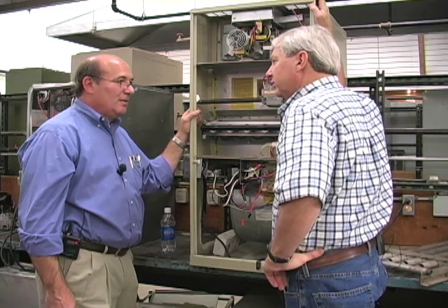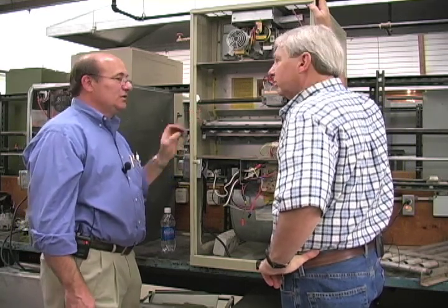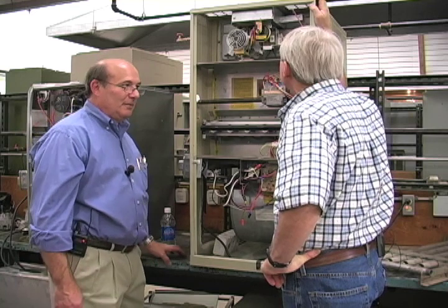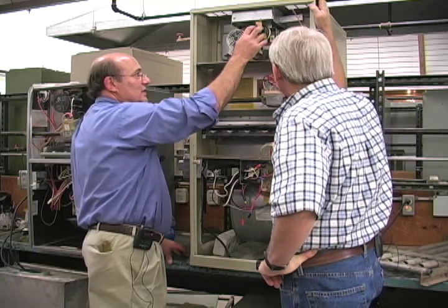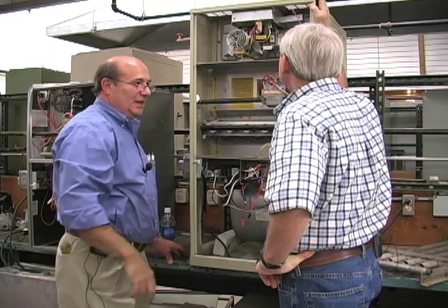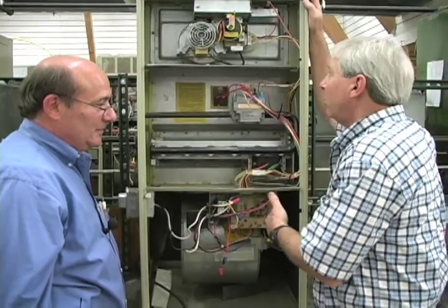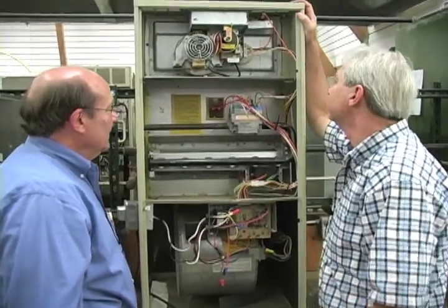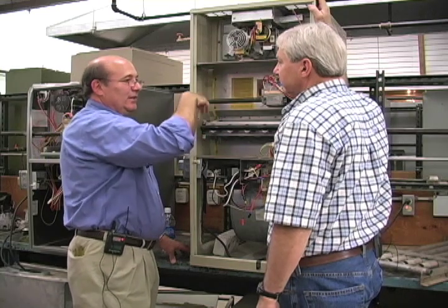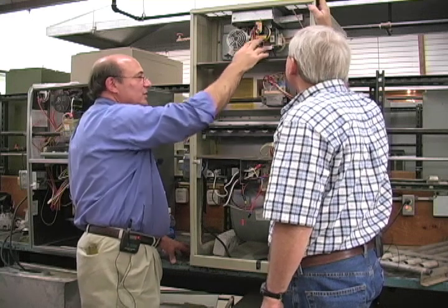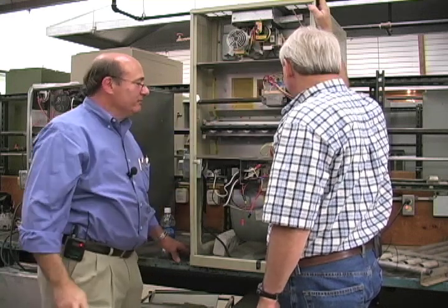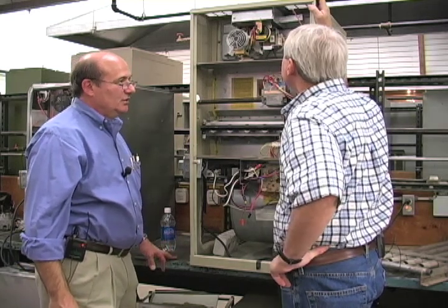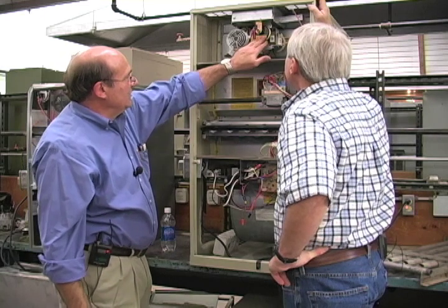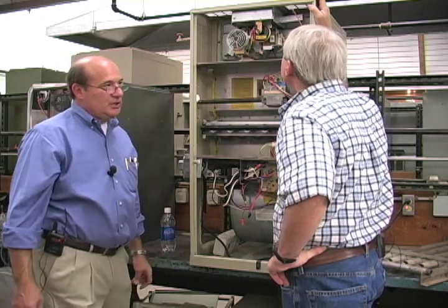But the good part about that is that the failure would be that the furnace won't come on. It won't develop enough pressure to close this switch and enable the gas system. So it won't go the opposite way. It might go through the purge part of the ignition, but it won't actually ignite. Right. Okay. It'll bring up the combustion blower and everything will go, but we won't ever close this switch, so we won't ever get a gas valve to open. Right. So manufacturers, when they first came out with them, and I think they still do, offer a high altitude conversion, which is basically to change out the module on these pressure switches.